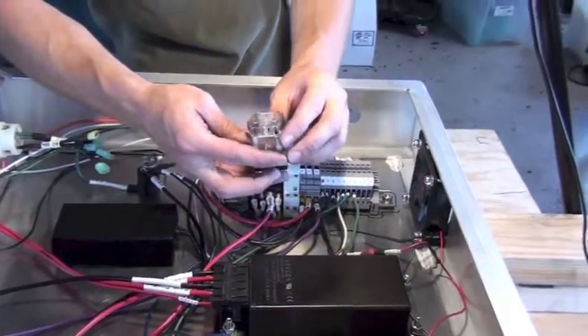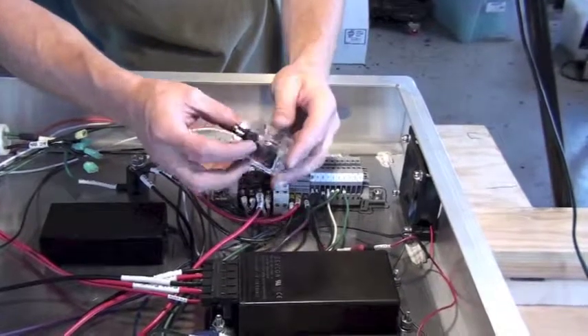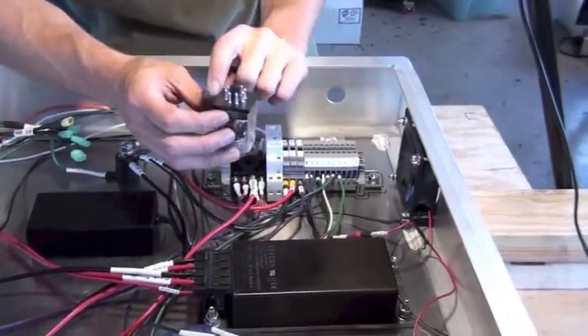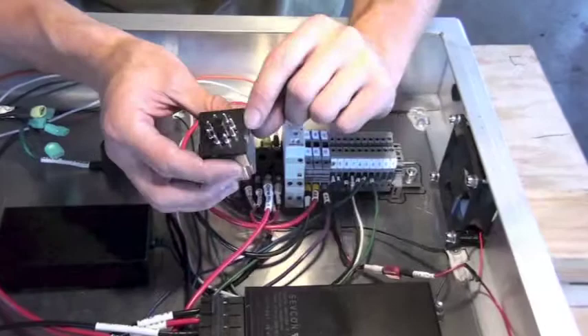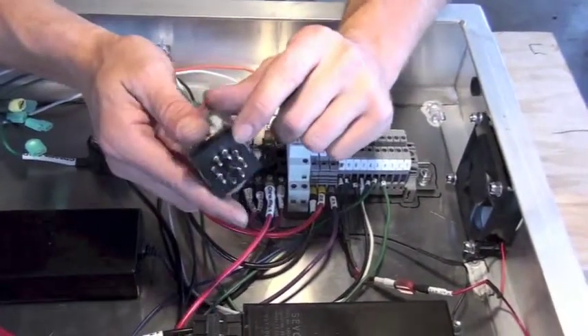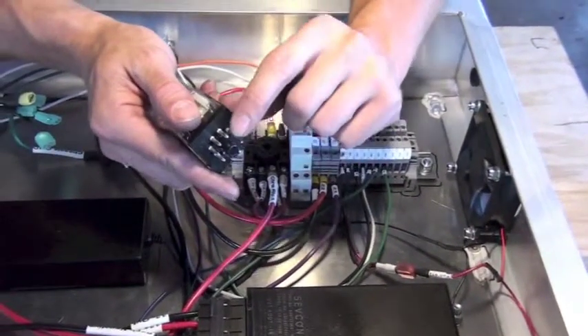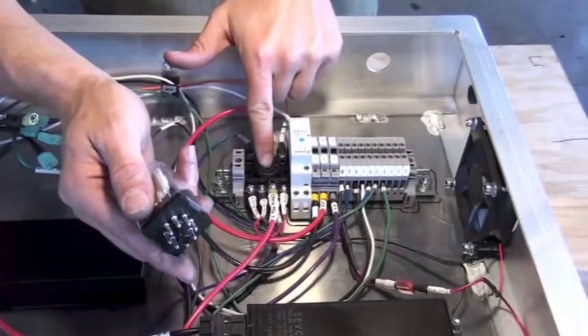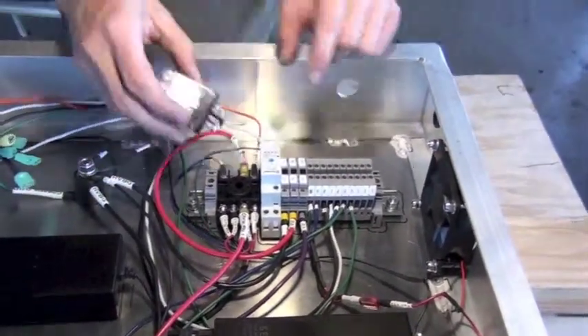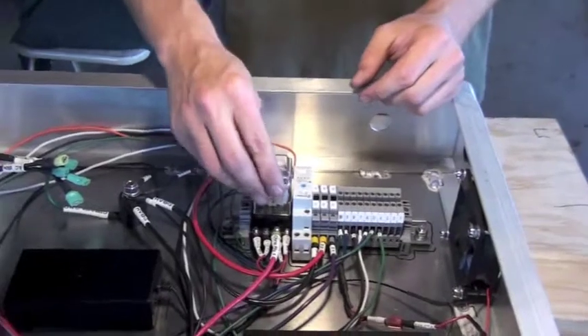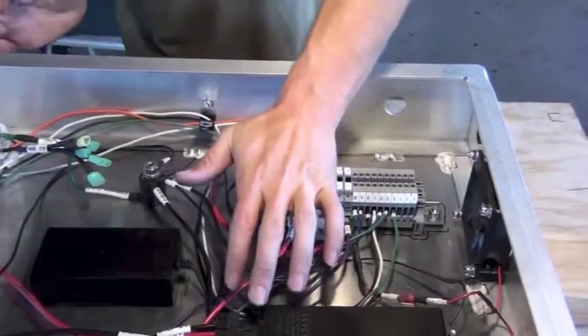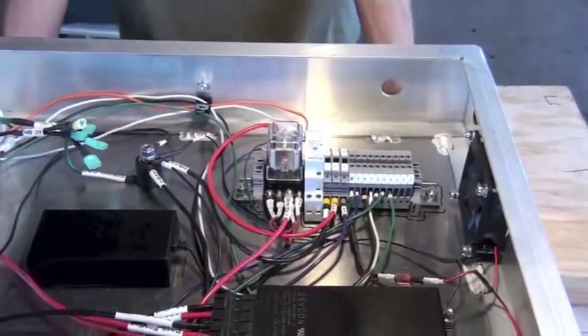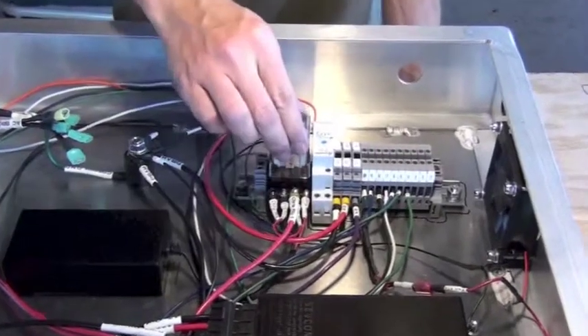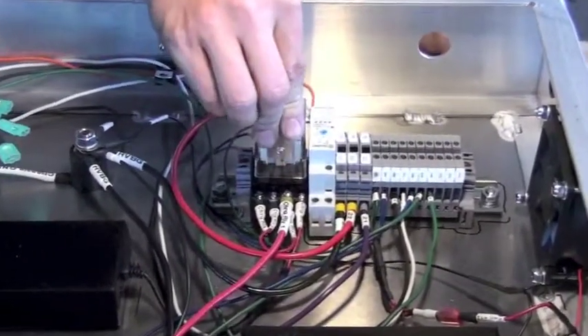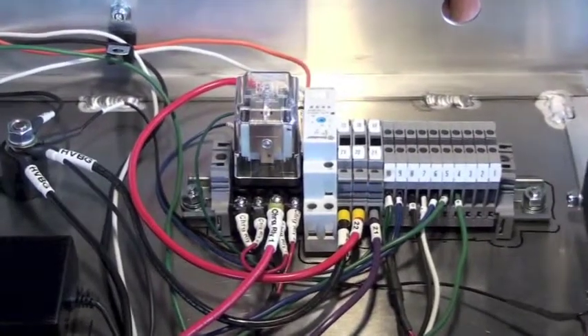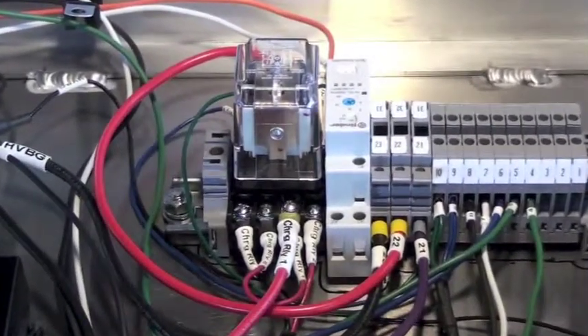Now we can install our charger relay into its receptacle. You'll notice that the 8 pins match up with the 8 pin openings in the receptacle, but there's also a key slot that lines up, so you can only put this relay in the correct way. It only fits in one way. You just push it into place and it does its job to switch between different components in our system. So we've wired up our charger relay and completed that circuit inside the high voltage control enclosure.